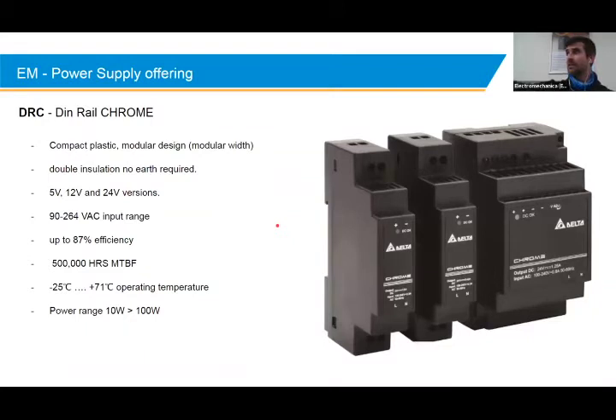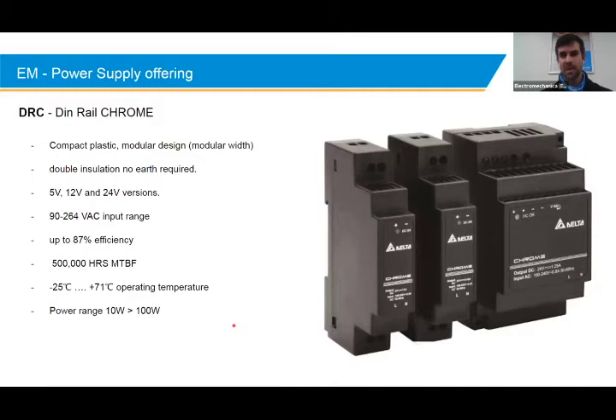Looking at the DRC, DRC DIN Rail Chrome power supply, it's a compact design, it's modular, has double insulation, so there's no earth terminal required. Comes in 5, 12, and 24 volt versions, as you can see on page B58. Nice wide AC input range, a decent efficiency of 87%, decent mean time before failure, and it's also very well priced. It's got a great operating temperature range, -25 to 71 degrees, and a small power range of only 10 to 100 watts. But great compact power supply, perfect for your DB boards, modular package. The widths are modular. I think it's 18 mils as your standard modular design.